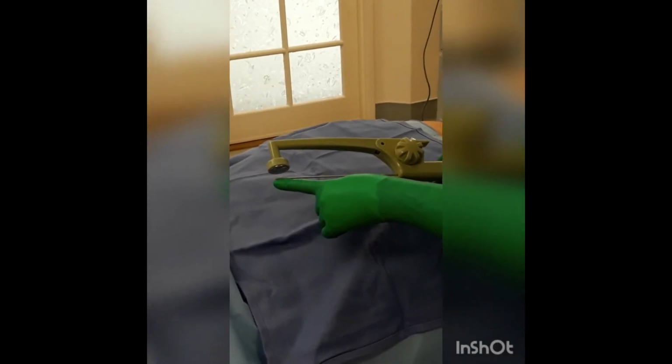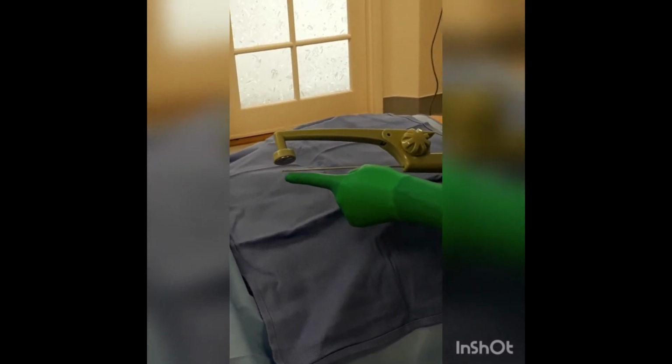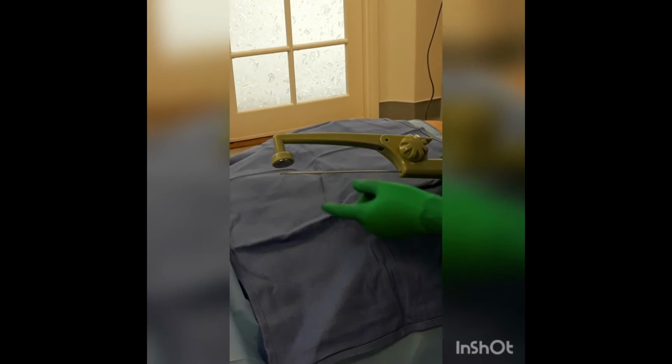This is the BodyTite handpiece. It has an internal electrode and an external electrode. The internal electrode generates the radio frequency energy and is transferred to the external electrode through the adipose tissue. This is meant to coagulate all the soft tissue, including the fibroseptal network, which is important for contracting the skin. The device has a control on it, which are numbers from 1 through 6.